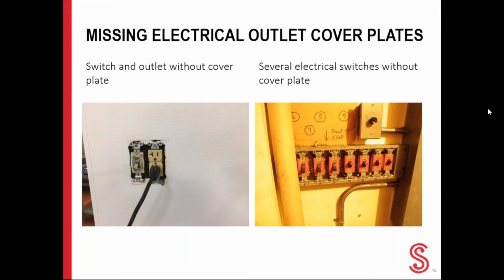Switches and outlets without cover plates will likely become a dust trap and ultimately a fire hazard. Lint and dust act as kindling when they accumulate, and uncovered electrical outlets are lint and dust accumulation spots. Cover plates are intended to contain fire and prevent electrical shock from exposed wires. Cover plates should be installed or replaced when missing.